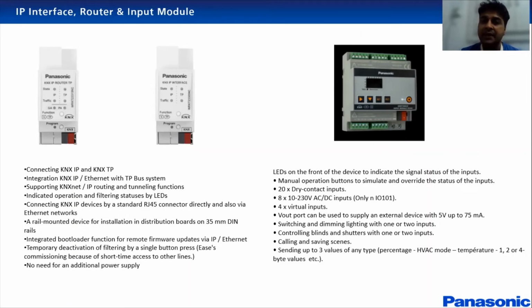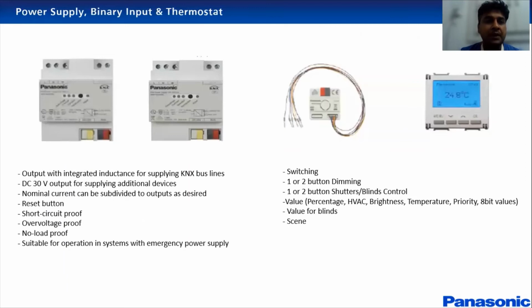And this is an input module. We have 20 gang, 20 inputs or outputs available. So you can configure this again on ETS based on your requirement. These are the power supply modules that we have, both in 320 milliamp and 640 milliamp. These power supply modules also have an additional 30-volt output to power any additional devices like your keypads or the touchscreen. If you require any additional power, that can be powered by using our power supply modules. And short circuit and over voltage protection are provided with this.